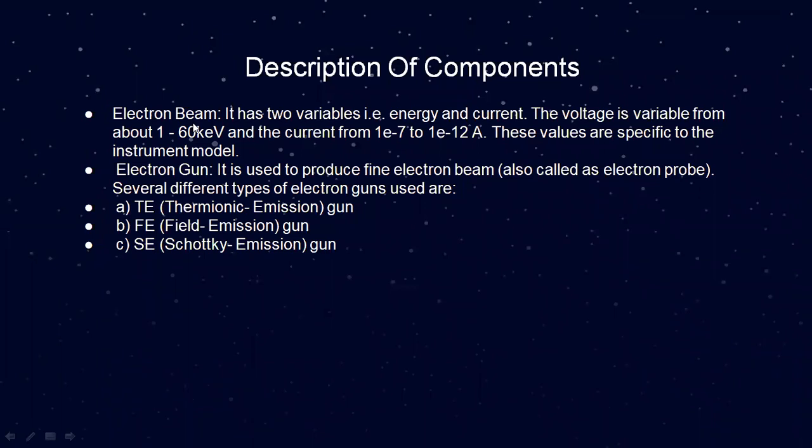The electron beam has two variable parameters: energy and current. The voltage is variable from about 1 to 60 kV and the current from 10⁻⁷ to 10⁻¹². These values are specific to the instrument model. The electron gun is used to produce the fine electron beam, also called an electron probe. Several different types of electron guns are used: thermionic emission gun, field emission gun, and Schottky emission gun.